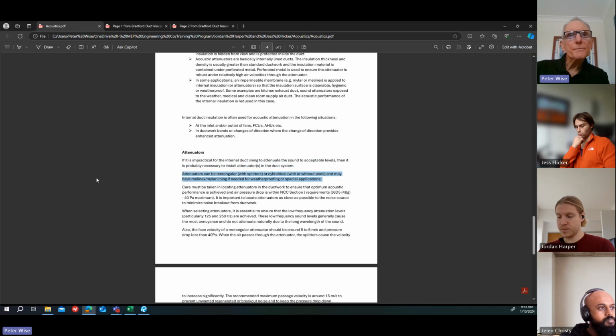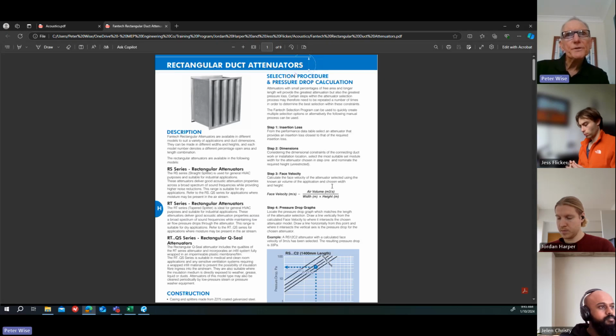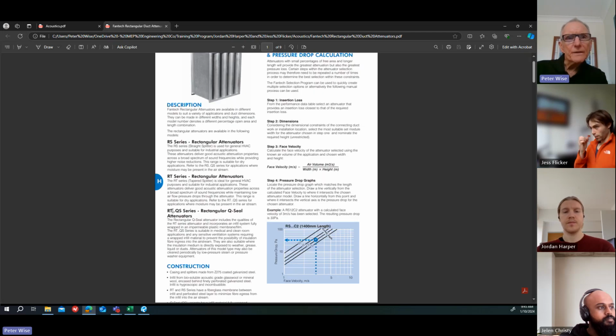So attenuators can be rectangular with splitters or cylindrical, with or without pods, and may have Melinex or Mylar lining if needed for weatherproofing or special applications, which I talked about before. So I'll just show you some extracts from the Fantech catalogue, in case you haven't seen what an attenuator looks like yet. So there's the two types, rectangular duct attenuators. There's two types here. There's an RS series, which has got straight splitters, or there's the RT series, which has got the tapered splitters. And then there's RTQS. That means it's a tapered splitter. QS means Q-Seal. That's a Fantech brand. Q-Seal is with the Melinex lining. Basically, that's all that means.